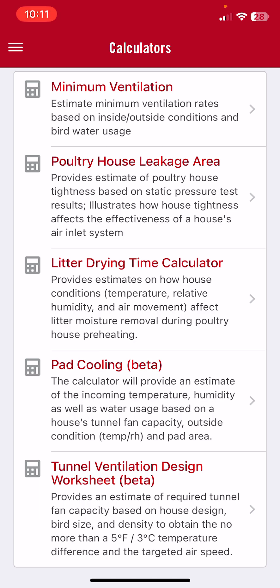The tunnel ventilation design worksheet provides an estimate of the required tunnel fan capacity based on a poultry house's overall design, construction, insulation levels, bird size, and density to obtain no more than a five degree temperature difference, as well as the tunnel fan capacity required to produce a targeted airspeed of whatever the user wants to input.